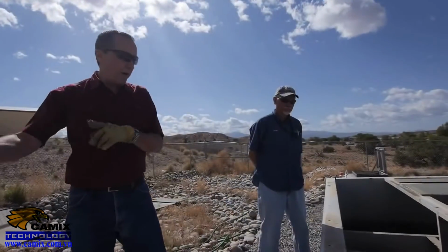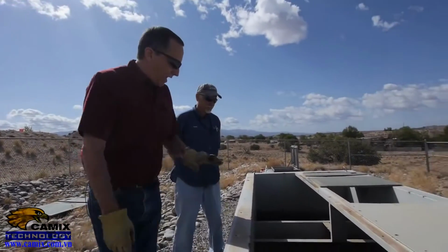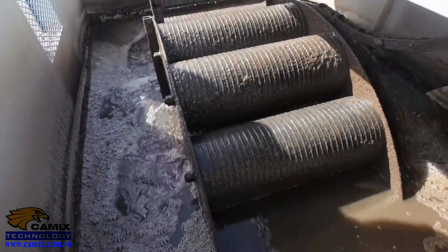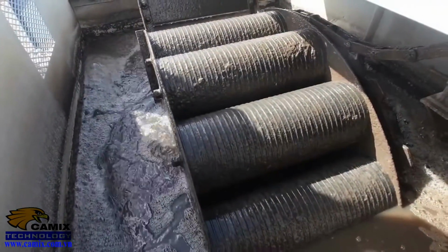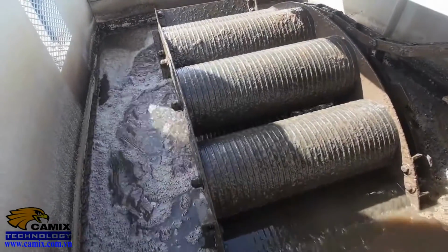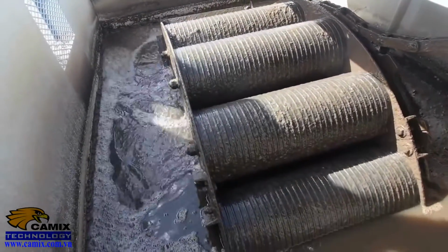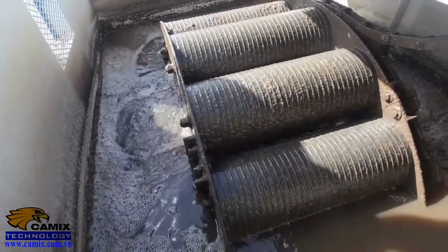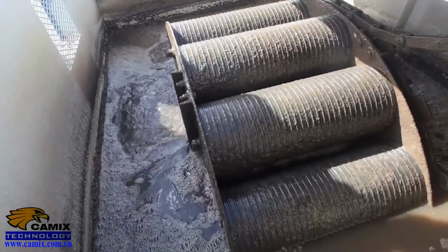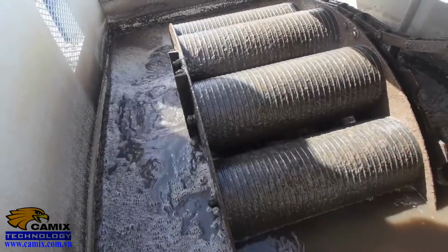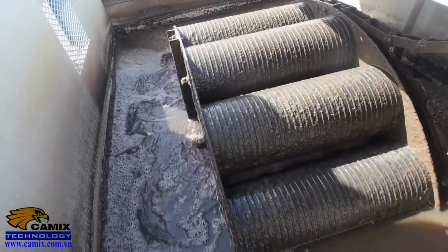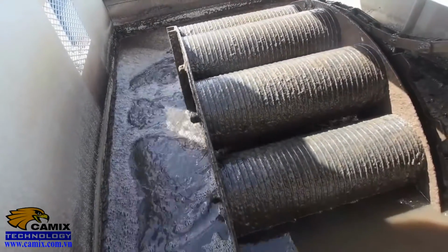Whatever's left over from primary flows into this basin, and you can see the air rotor turning. There's 2 processes going on here. The gray shaggy biomass that's on those drums is the fixed film, and that's a certain kind of bacteria. And then there's also an activated sludge process, which is that brown mixed liquor that those rotors are turning in. And what's happening is as that rotor turns, it picks up the mixed liquor, and as it slowly rotates, when it gets above water, it spills that mixed liquor out and it aerates this top section.